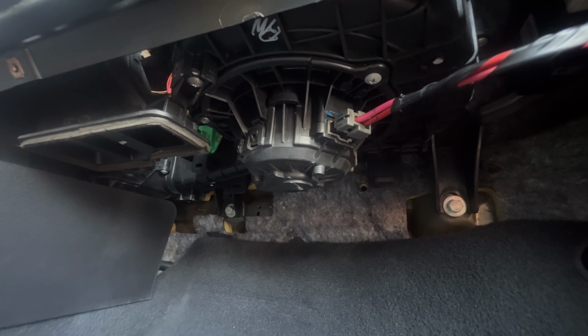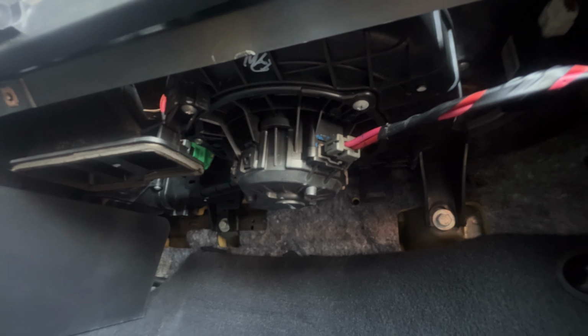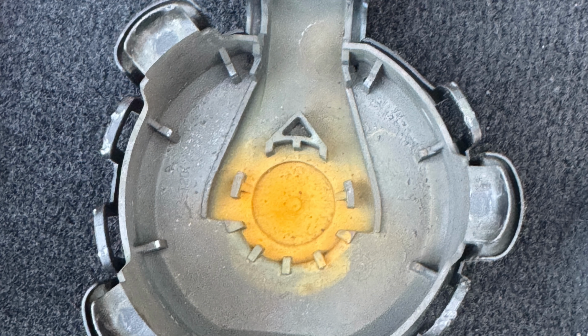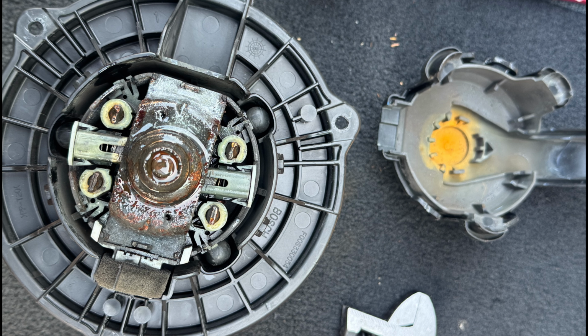In my case, after removing the lower cover, I saw that the bottom of the motor was rusty, which caused it to seize. I removed the fan blade propeller and cleaned the inside of the motor with electrical contact cleaner. Then I sprayed the rusted area where the lower cover had been with WD-40, carefully and lightly. Finally, I reassembled the motor exactly as it was.